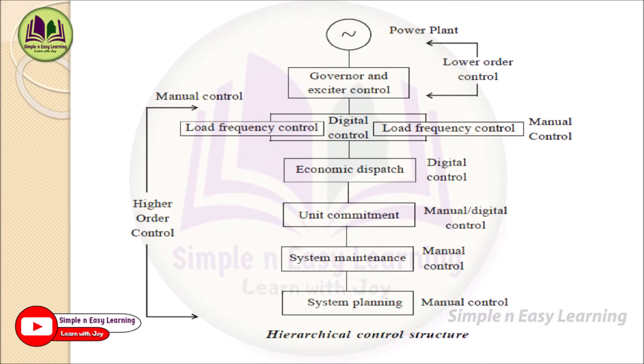Economic dispatch determines how to dispatch load in an economical manner using digital control. For example, if 6 units of 100 megawatts each are available and only 300 megawatts is required, the power can come from units 1-2-3, or 1-2-5, or 1-3-4, and many other combinations. Out of all those probabilities, we determine which combination is most economical using available methods — this is called economic dispatch, done by digital control.